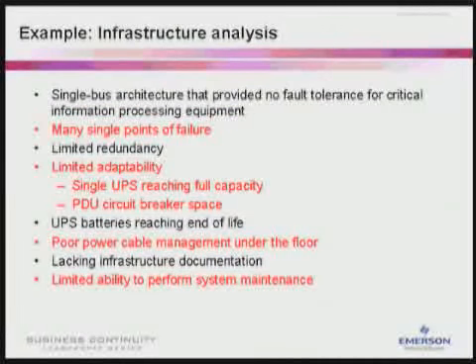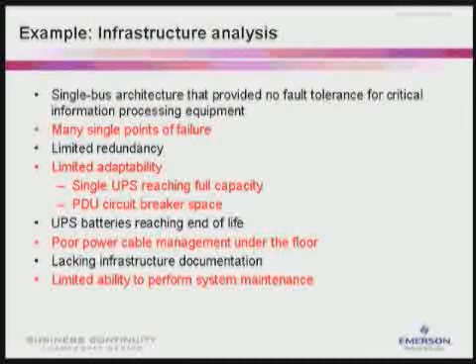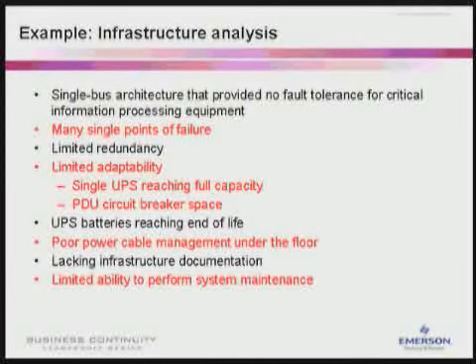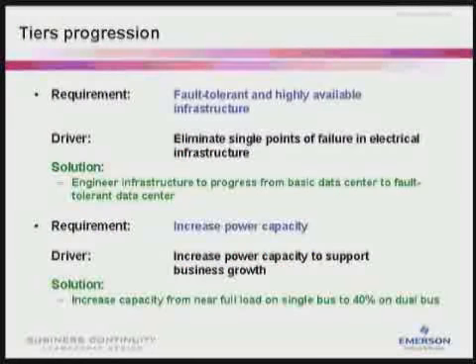Now let's do an infrastructure analysis. This was an actual data center that needed to improve its capacity, redundancy, and availability. There were many single points of failure. There was limited adaptability. There was a single UPS reaching full capacity, and the data center was running out of PDU circuit breaker space. Power cable management under the floor was a challenge, and there was limited ability to perform system maintenance.